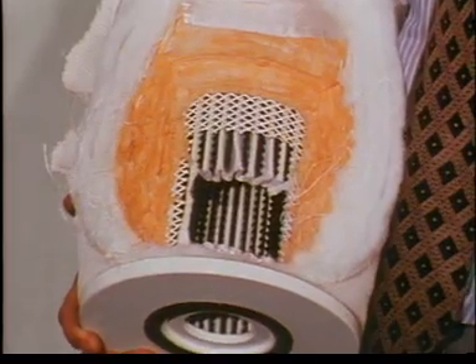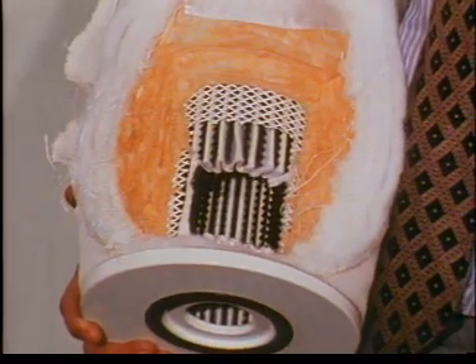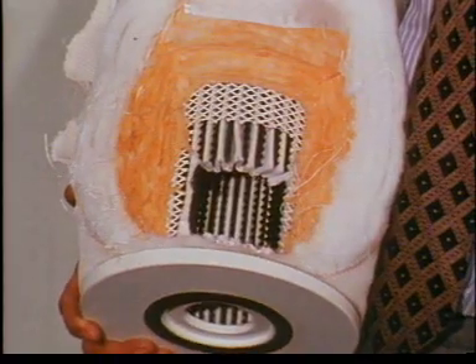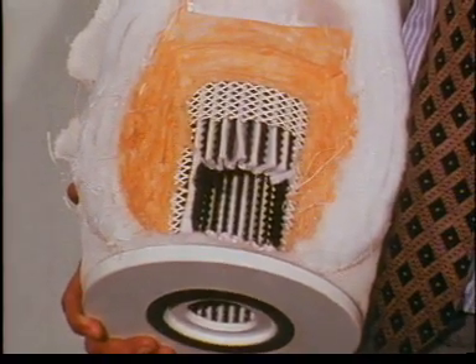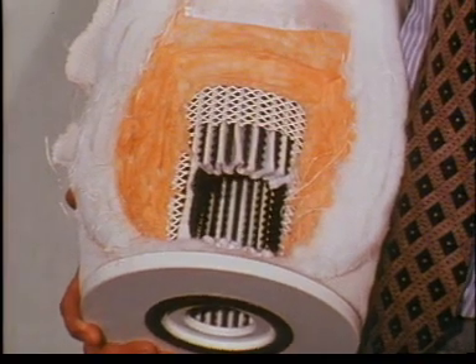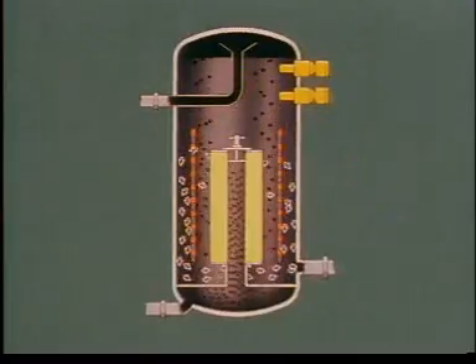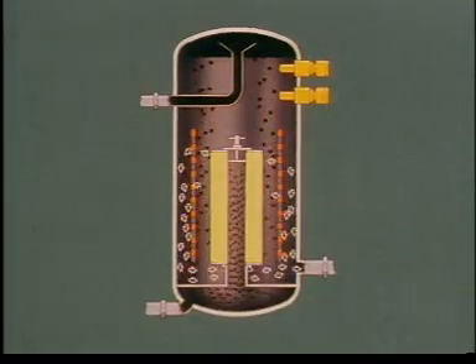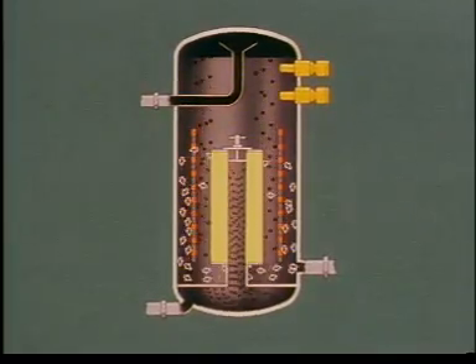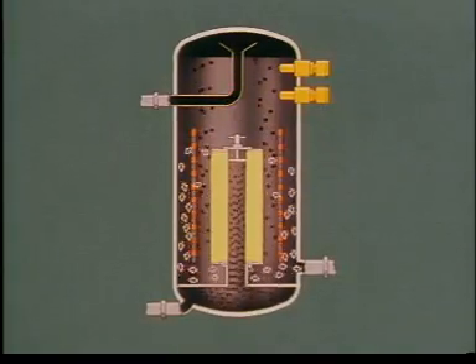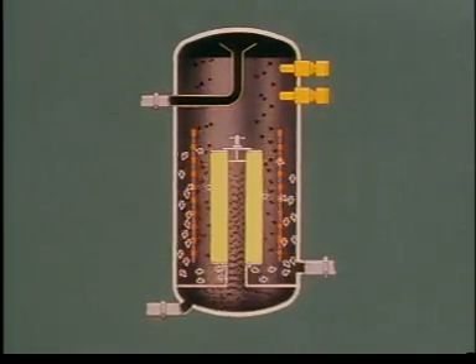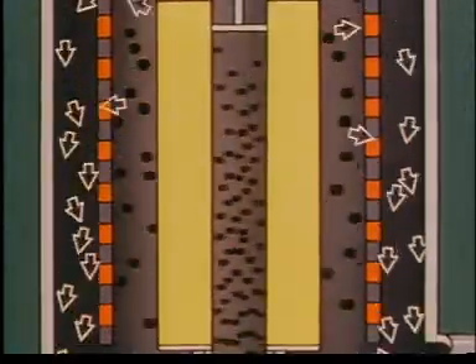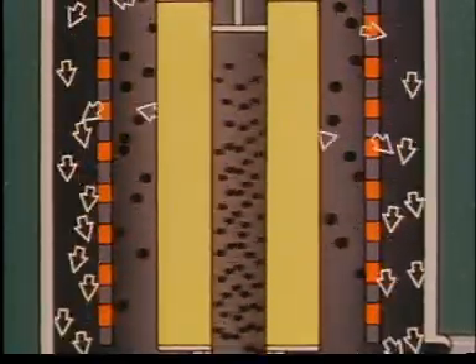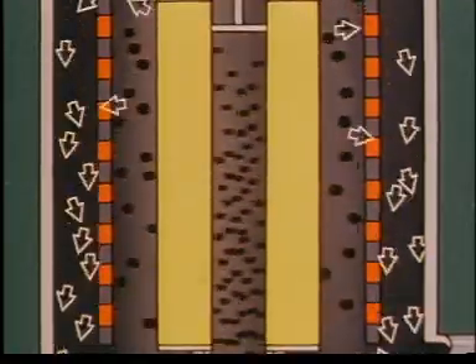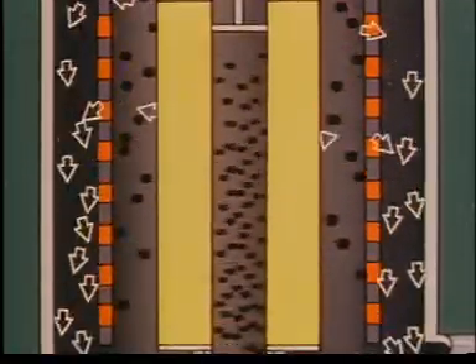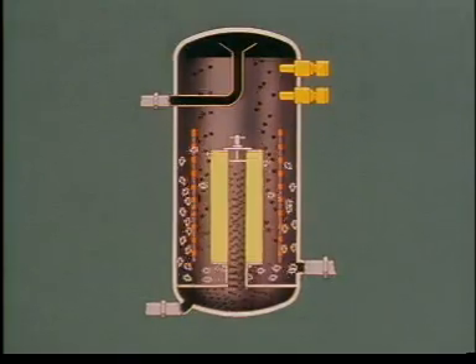Small globules of oil stick to the glass fiber and in time coalesce with others, forming larger globules. In due course, pressure from the inside forces these larger globules right through the cylinders to the outside, where they rise rapidly. Outside the coalescer elements, and there may be a number of them, depending on the required throughput of oily water, is a fine mesh stripper made of nylon. The design flow is such that oil globules will bounce off this and continue their upward path, while the water will pass through.